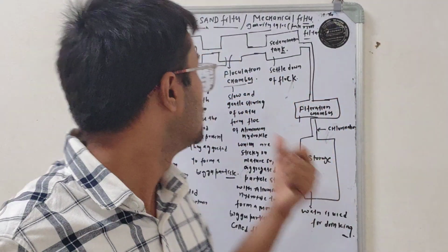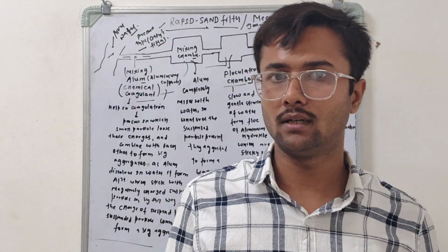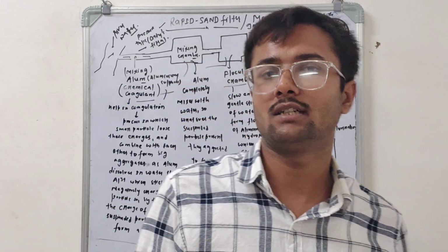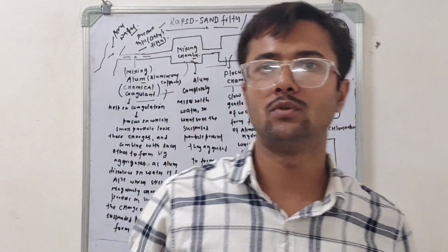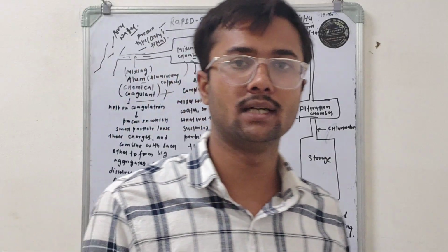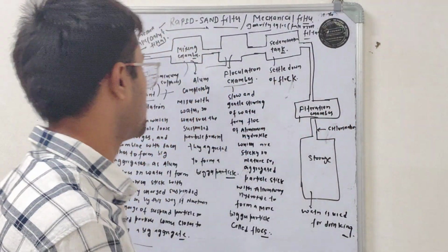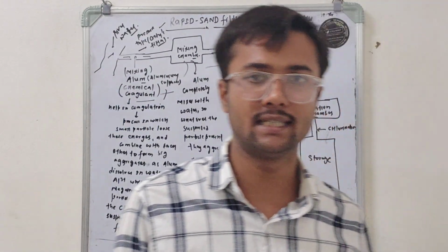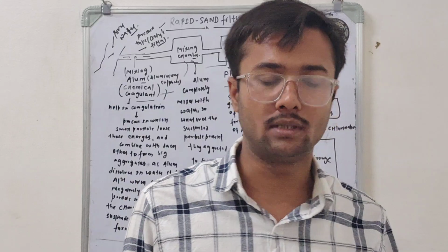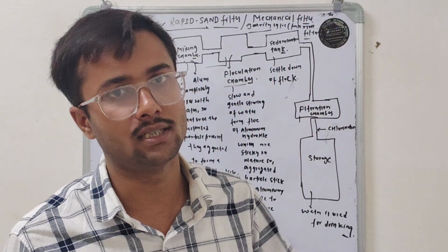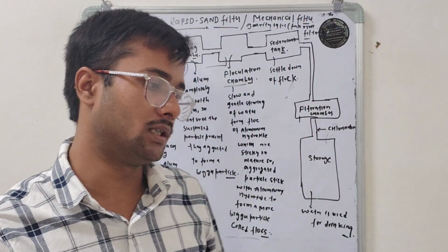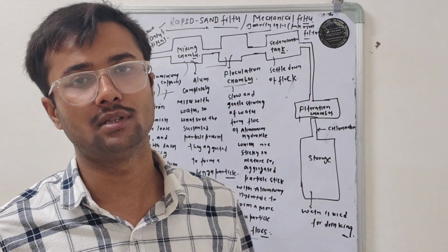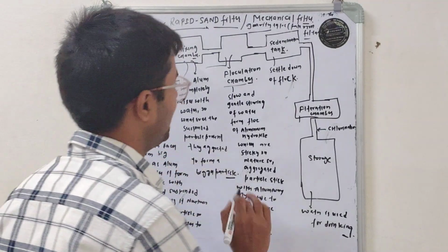So in the flocculation chamber, whatever coagulated particles are present start sticking to this aluminum hydroxide and form even bigger particles, and this process is called flocculation. In flocculation, with the help of aluminum hydroxide acting as the flocculating agent, the size of the impurity particles increases. I mean the diameter of the particles increases, and smaller particles change into bigger particles. In simple terms, that's fine.